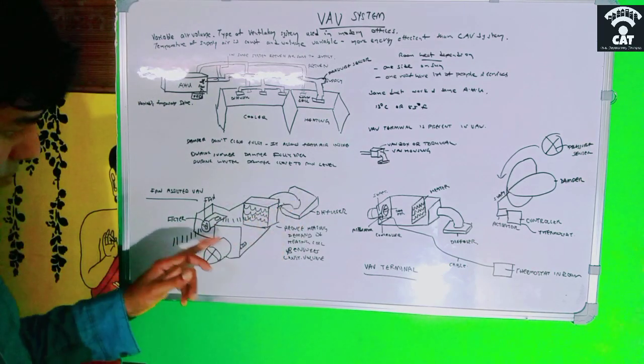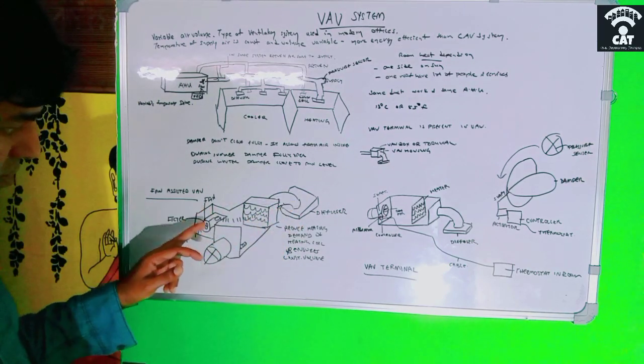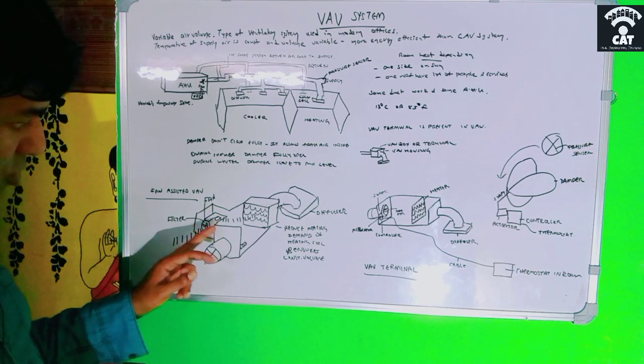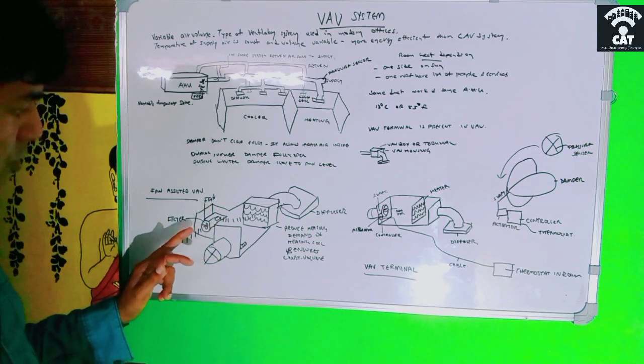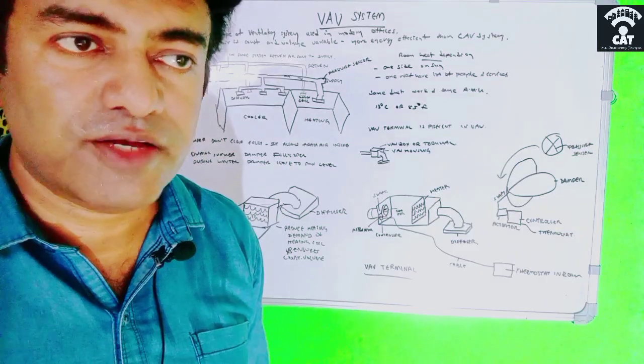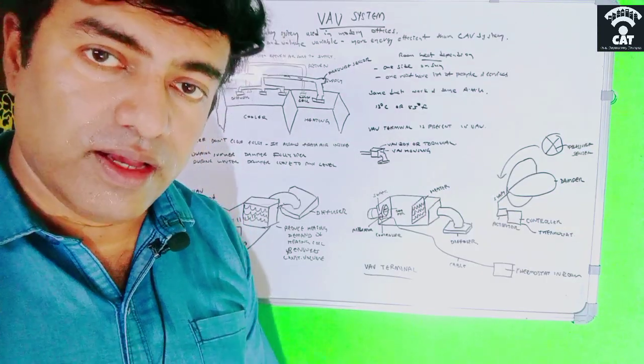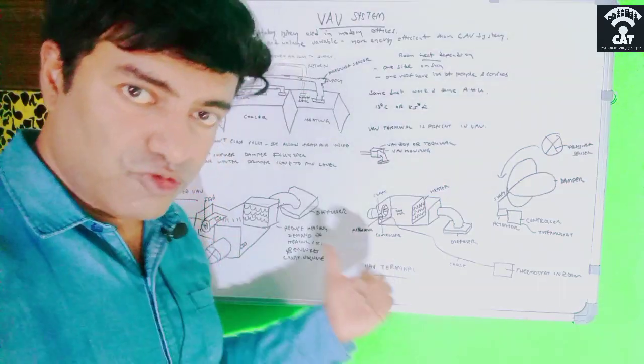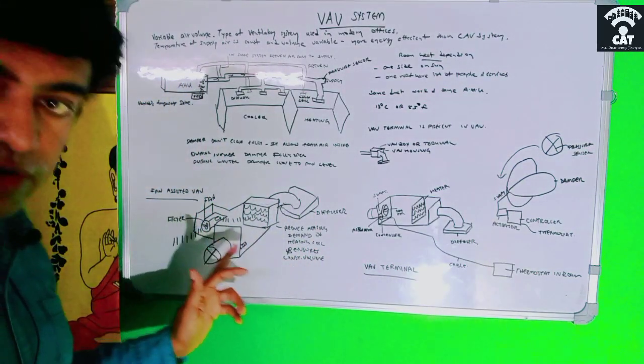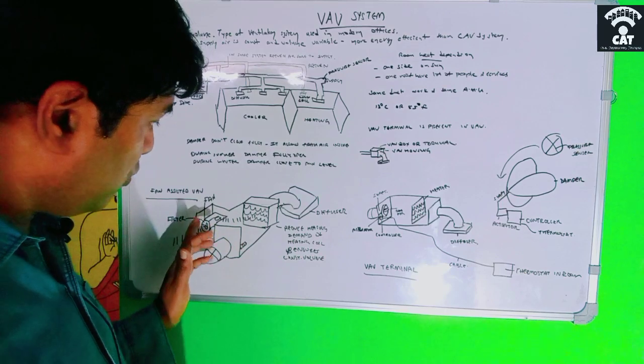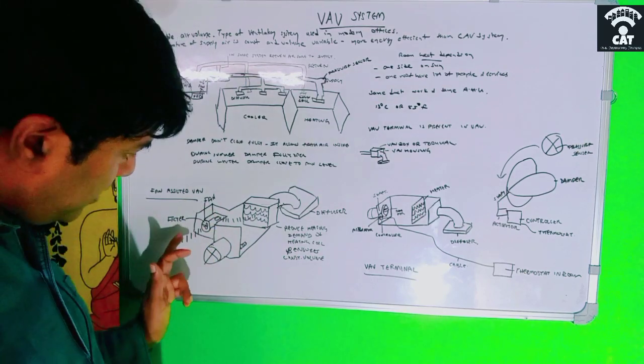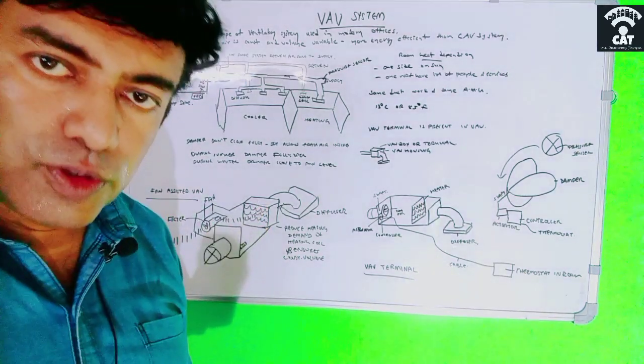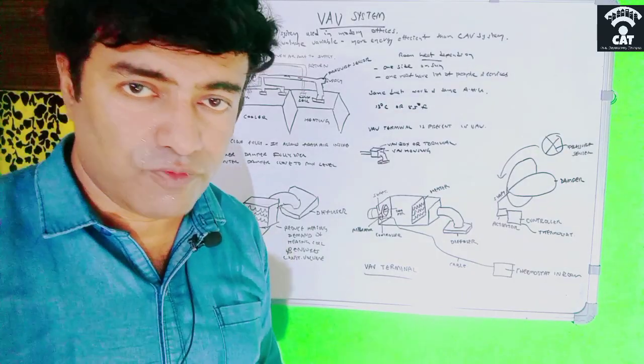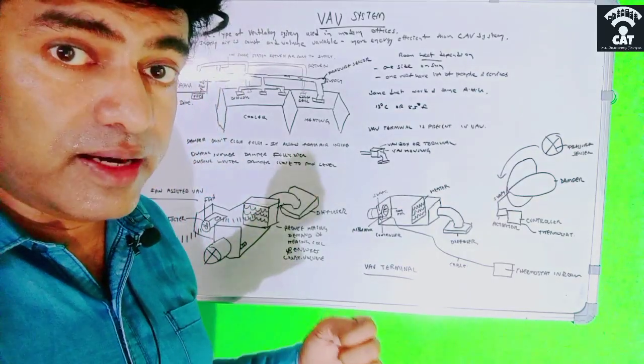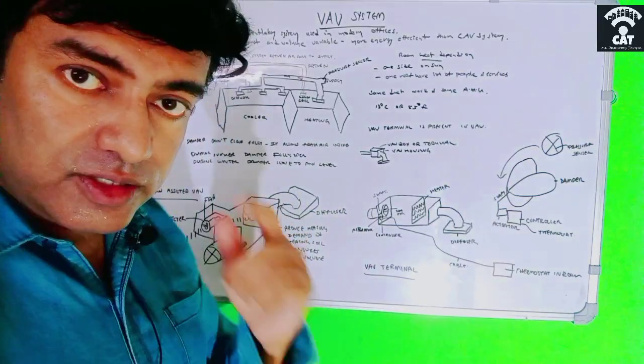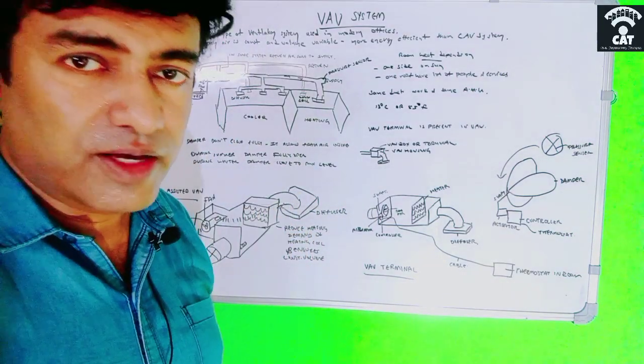So this is the usual VAV system, but here there is an attachment of a fan with a filter to this system. This is a fan which has got a filter too. Here the VAV takes the room air again into it through this fan. There will be a filter there, which will filter out the impurities in the air, and then with the help of the fan it will take the air directly into the heater, so that the VAV system can keep a constant volume of air and also reduce the demand of heat for this heater. So in order to save energy, we are using it like that.